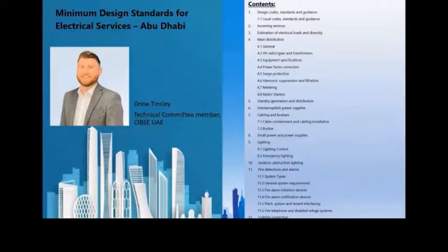In terms of equipment specifications, there's a lot of guidance in these guides that draws the eyes to specification items for things like RMUs and switchgear, and which guidelines you should be using for those, which might be more international standards. It aims to assist the engineer in terms of where to find that information, covering standard things like ingress protection for MDBs and minimum forms of construction, such as form 4B type 6 for MDBs, and the nuances of DBs rated over things like 200 amps, which require their own spaces.